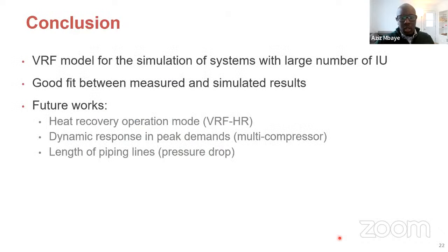So for conclusion, we first developed a VRF model that is able to simulate systems with a large number of indoor units. And the comparison that we just discussed here showed that we have a good fit between the model and the measured data. And in order to improve the model accuracy, we need first to extend it toward the use of multi-compressors to help capture better the power variation, especially in peak demands.